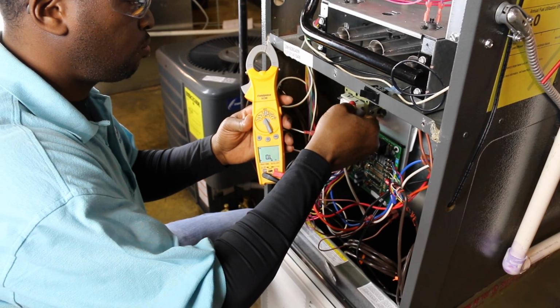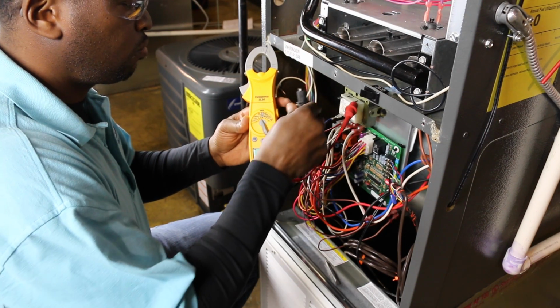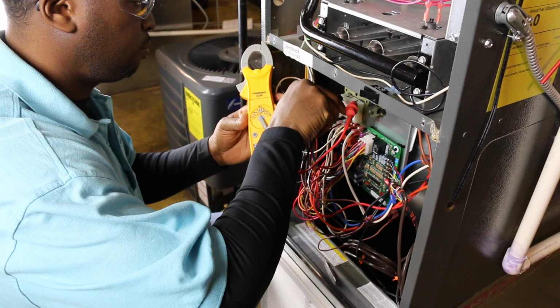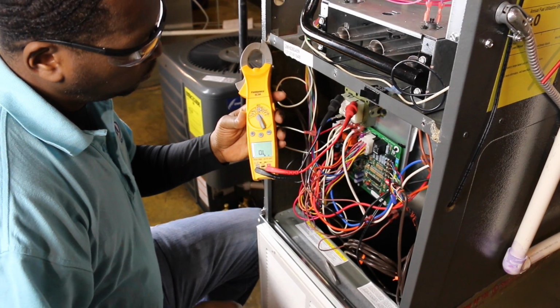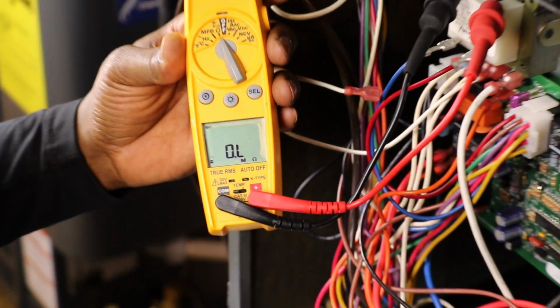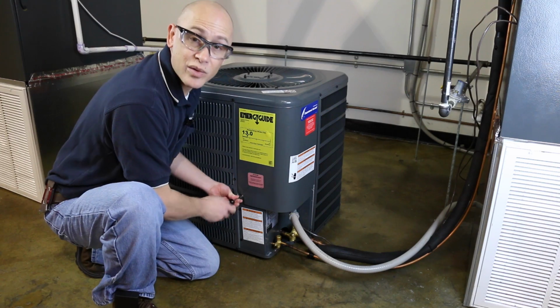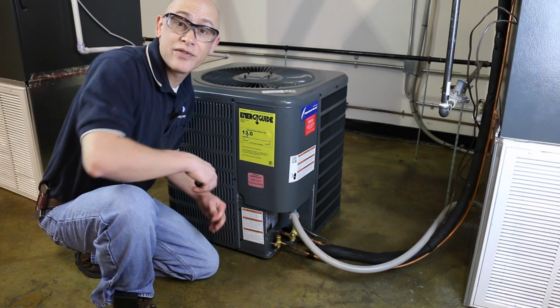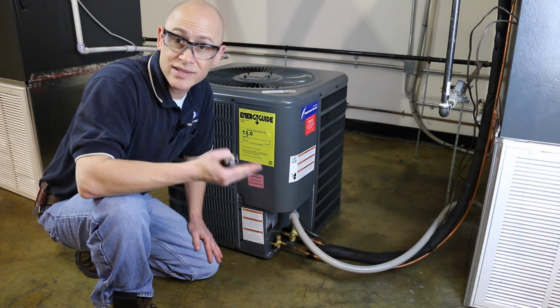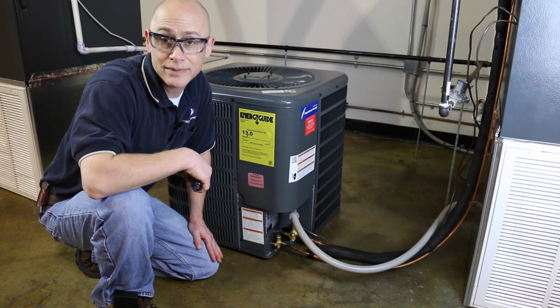Here is an example of a faulty transformer. As Darren checks the primary side for continuity, he finds that it's reading open line, indicating that the winding is open. You don't ever want to condemn a component without first verifying it with a meter. That way you can save yourself and the homeowner some time and money.